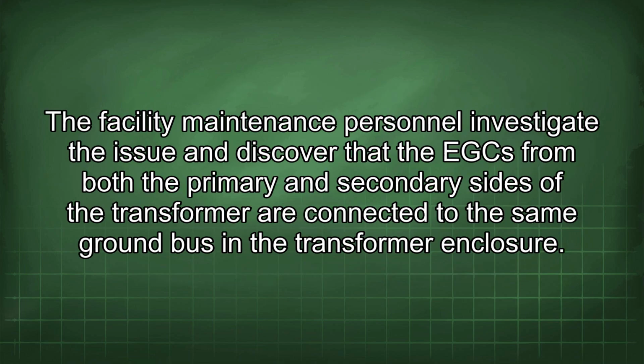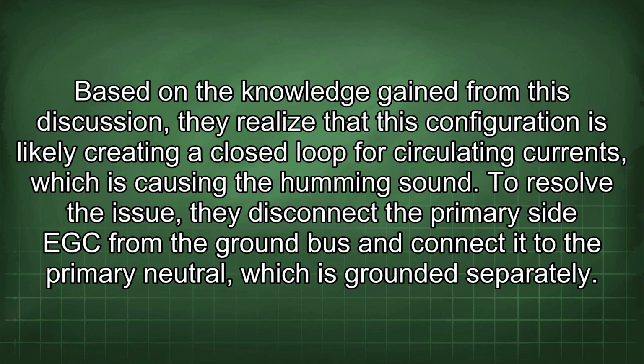The facility maintenance personnel investigate the issue and discover that the EGC from both the primary and secondary sides of the transformer are connected to the same ground bus in the transformer enclosure. Based on the knowledge gained from this discussion, they realize that this configuration is likely creating a closed loop for circulating currents, which is causing the humming sound.